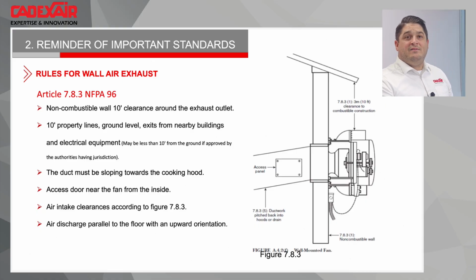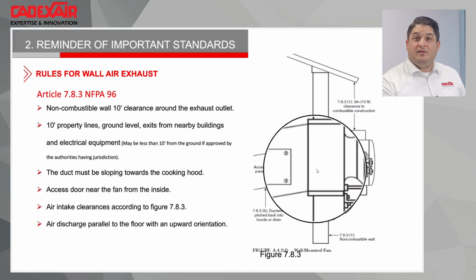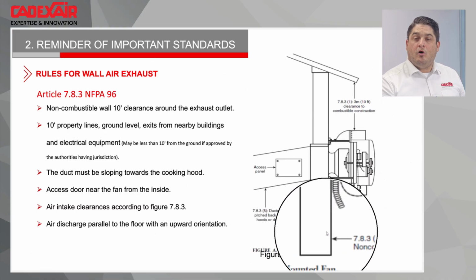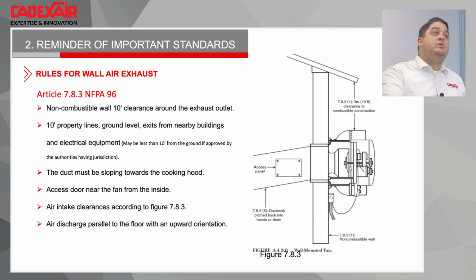And after that, you need to be 10 feet from the property line. I will say this one is not often followed in the big city, it's really difficult, so it's not fully followed by everybody. The duct needs to slope toward the cooking exhaust hood, because at the end, when you have your fan, if the grease flows, it will flow on the wall, and also on the louver. So you want the grease to go back to the hood, or to the fan, or to another lower point or drain that has been installed inside the ductwork.